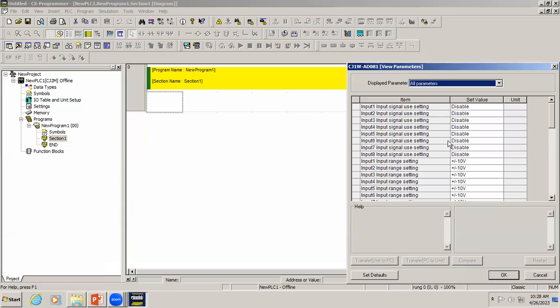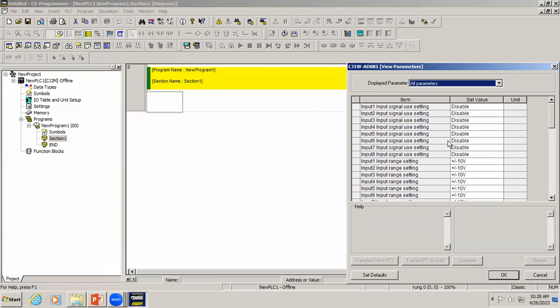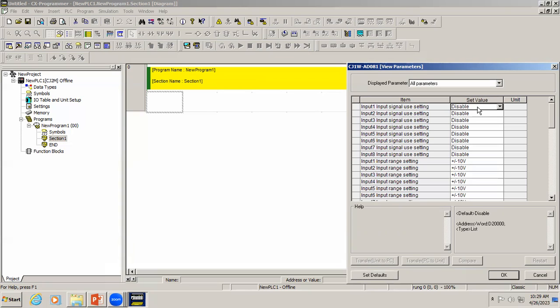Once we add it, double-click to open the properties. In there you can see input 1 input signal setting — we can select whether we are going to use it or not. If it is disabled and you connect an analog input, your PLC won't read the value. If you have 8 inputs and want to use only one, you must enable that one signal.